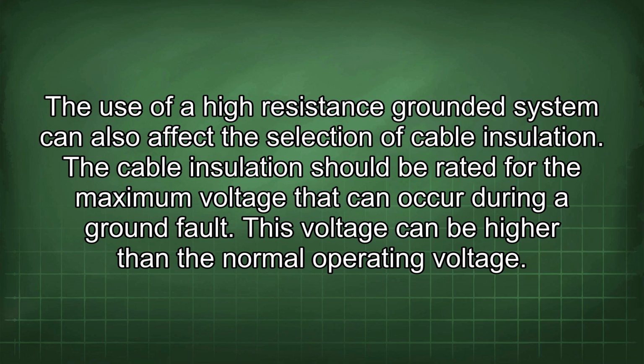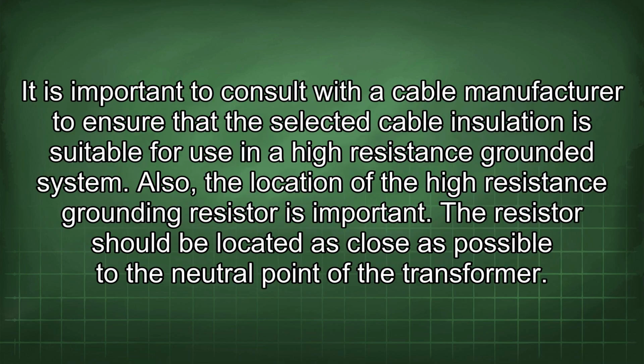The use of a high-resistance grounded system can also affect the selection of cable insulation. The cable insulation should be rated for the maximum voltage that can occur during a ground fault. This voltage can be higher than the normal operating voltage. It is important to consult with the cable manufacturer to ensure that the selected cable insulation is suitable for use in a high-resistance grounded system.